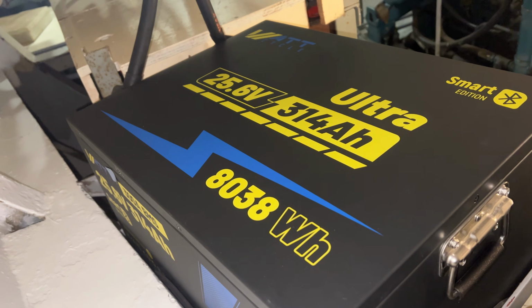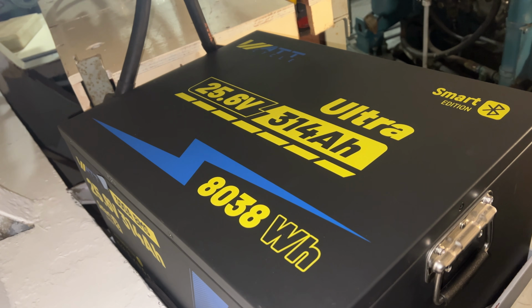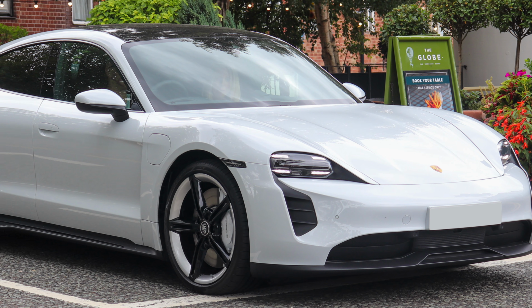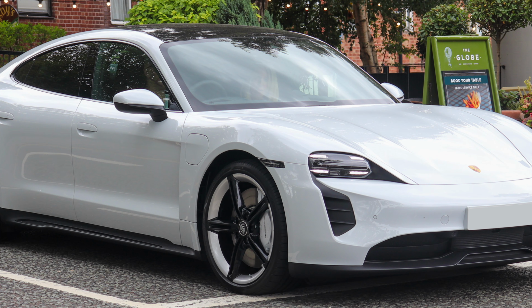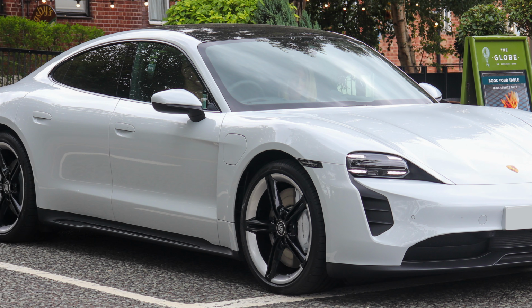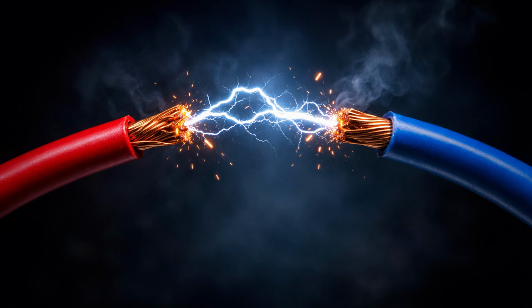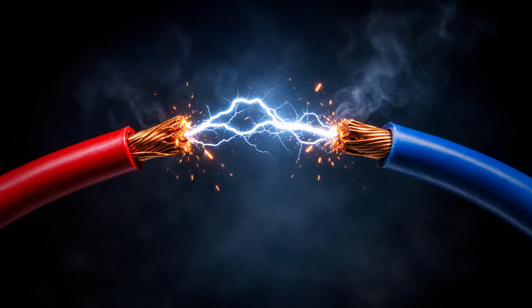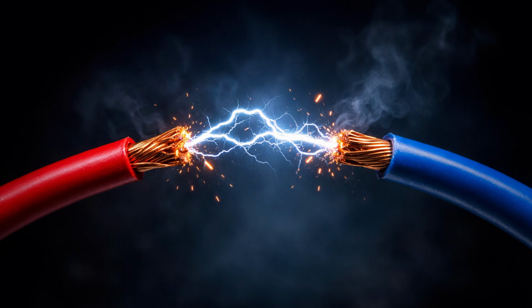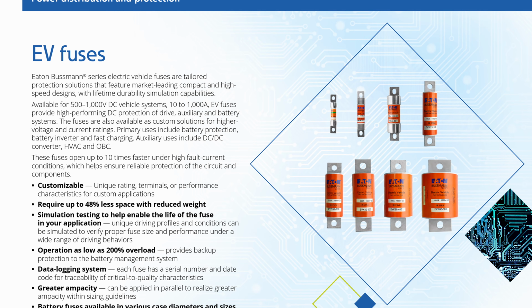That is not how it works with a battery that is meant to power an electric car motor. For starters, an EV motor does not run on 24 volts, but in a voltage range of 3 to 400 volts direct current. And some newer models even go up to 800 volts. But ours is in that first group. What does that mean? Well, touching a live 400 volts DC wire can definitely stop your heart. And the higher the voltage, the further electricity can jump through air. So everything in the system has to be designed and approved for that voltage.